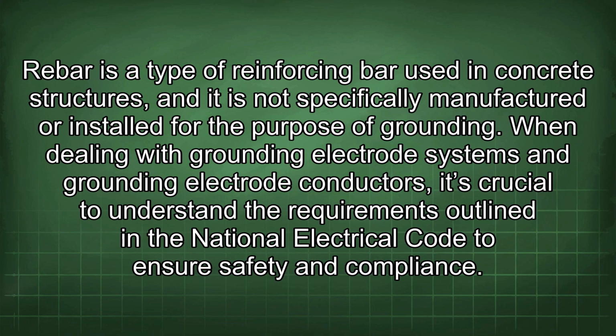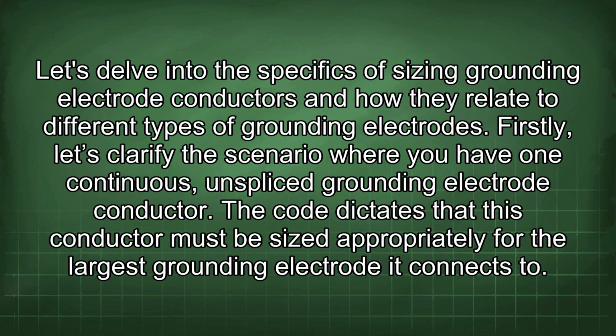When dealing with grounding electrode systems and grounding electrode conductors, it's crucial to understand the requirements outlined in the National Electrical Code to ensure safety and compliance. Let's delve into the specifics of sizing grounding electrode conductors and how they relate to different types of grounding electrodes. Firstly, let's clarify the scenario where you have one continuous unspliced grounding electrode conductor. The code dictates that this conductor must be sized appropriately for the largest grounding electrode it connects to.